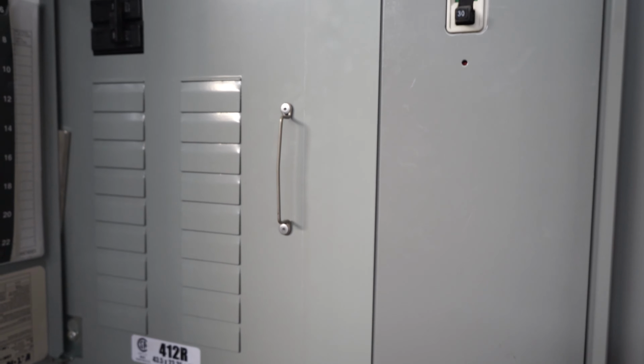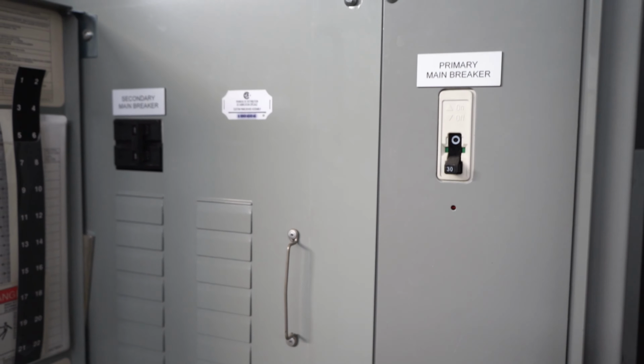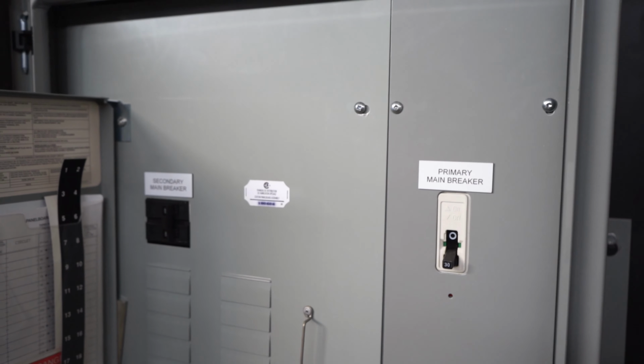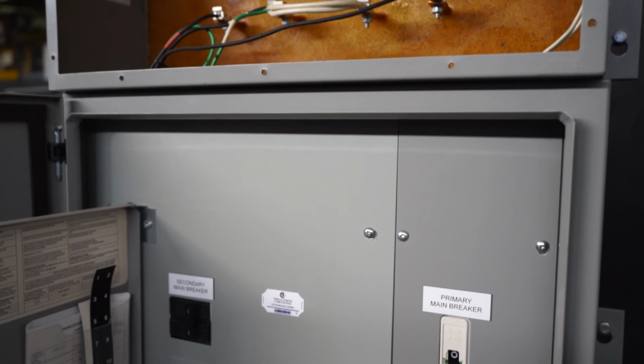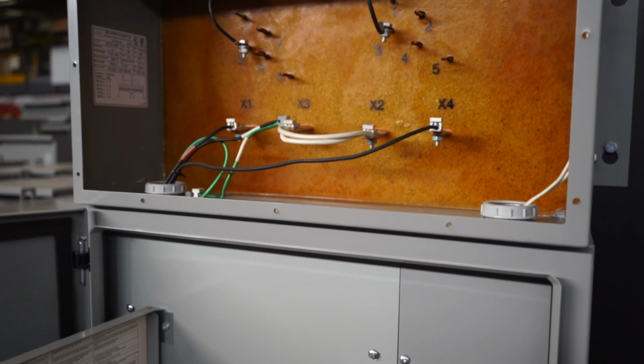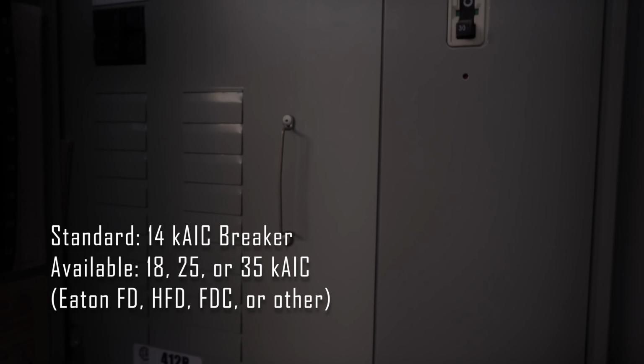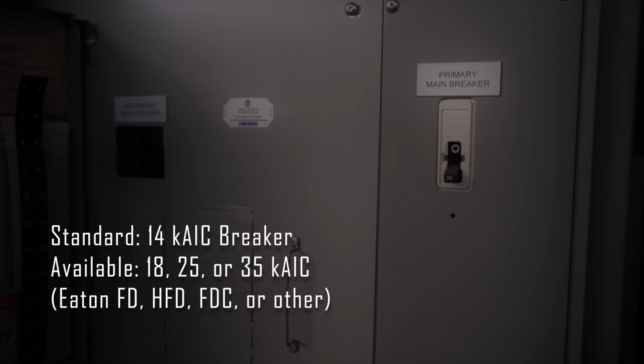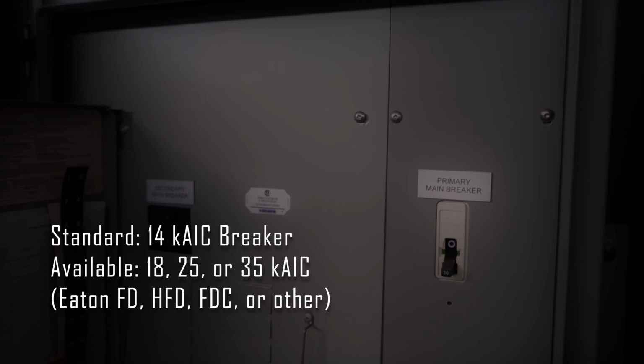An appropriately rated primary breaker with 14 kiloamps interrupting capacity is installed in the bottom panel board section to provide primary protection as well as an easy power disconnect. The interrupting rating of the incoming breaker can be upgraded to 18, 25, or 35 kiloamp ratings when necessary.